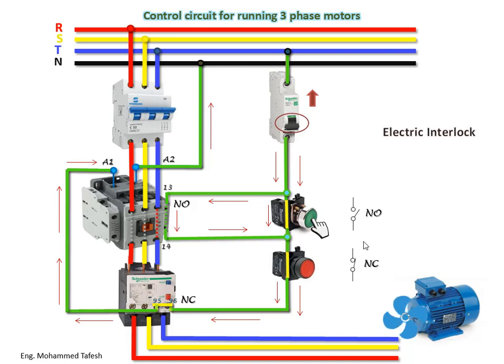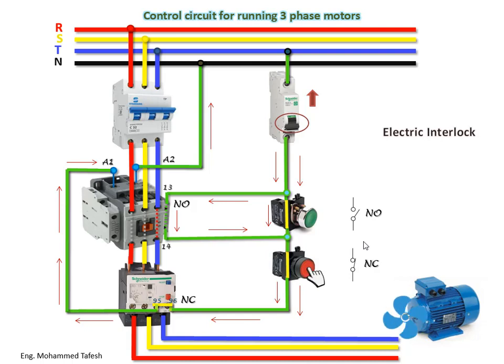Because contacts 13 and 14 were previously in the connected state due to magnetization of the contactor, the current will continue to pass through the interlock to the rest of the circuit. As soon as I lift my finger, the circuit will still run through the interlock path and the motor will continue to spin. If I want to turn off the circuit, I press the push button OFF, which opens the electrical circuit — as if cutting it with scissors.